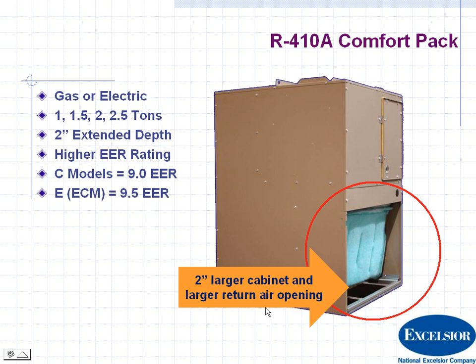It does have a patented furnace system, which we'll talk about here a little later on. The gas and electric, like we said, they're newer units. They've extended the depth on it to get a little higher energy efficiency rating, a little better airflow for the filter and cooling coil. Their C models, the CPG C models, are 9 EER, and their E models, the ECM models that have a DC motor, are 9.5 EER.